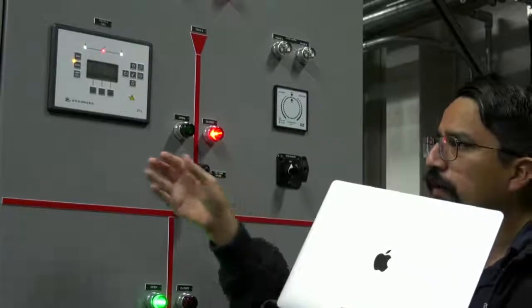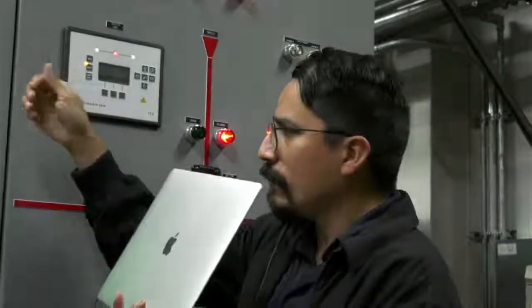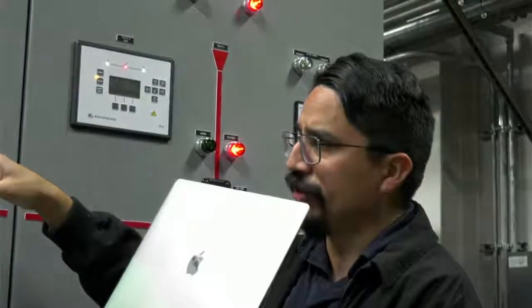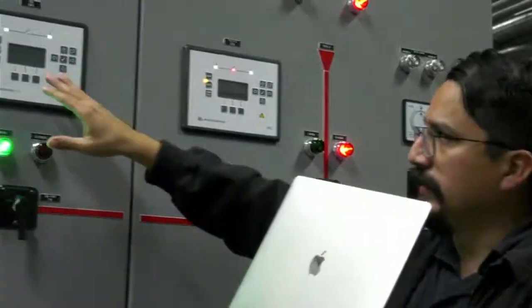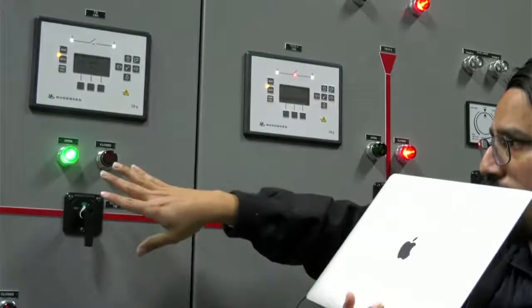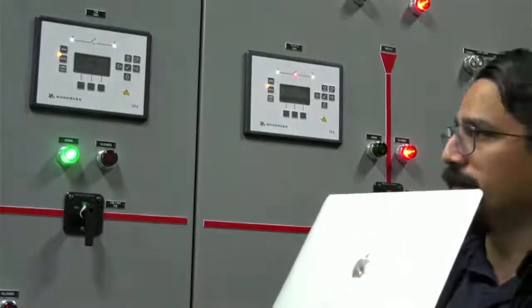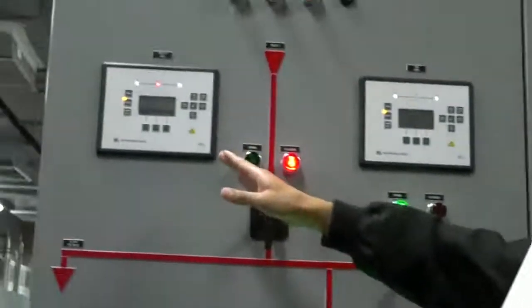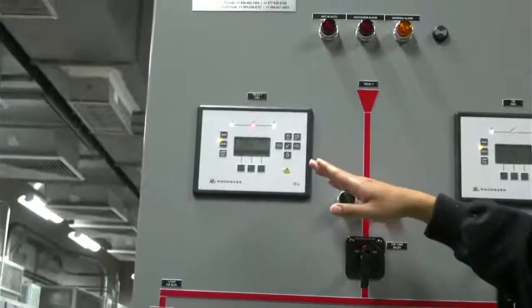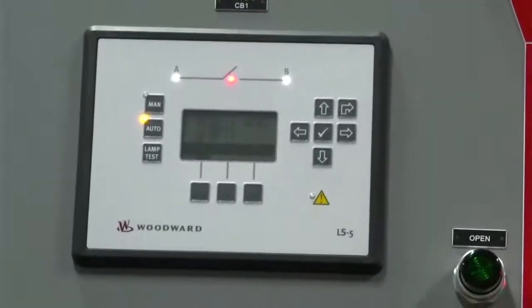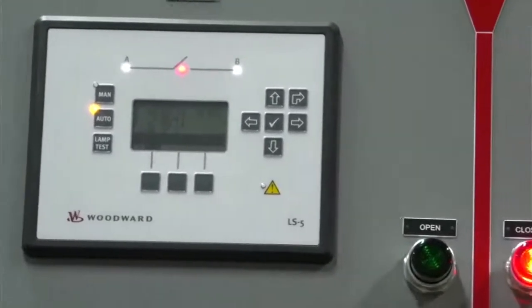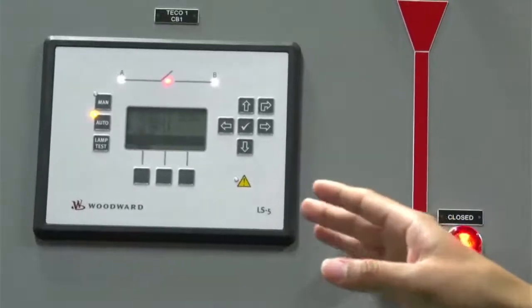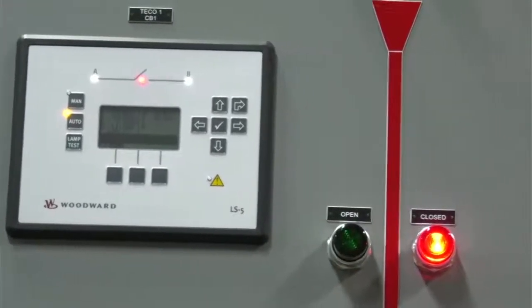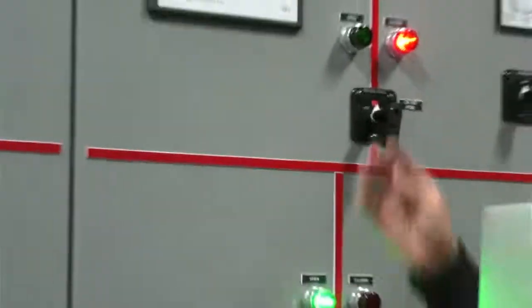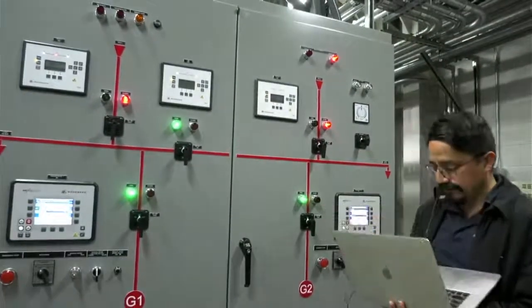This is the TECO. The same happens with the tiebreaker. So in any condition in auto, this LS5 is going to open or close the tiebreaker. The same with TECO 1: the LS5 controls and monitors TECO 1, can open the TECO circuit breaker, and is going to measure all the voltage and the frequency. Those are the EasyGen control and the LS5s.